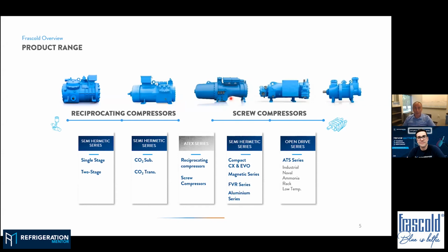Of course, the system and the charge has to be confined - it's an outdoor installation, and there are a number of safety measures to be followed. So it's not that you can put 70 pounds inside a supermarket, but it is possible. For pharmaceutical and plastic extrusion applications there's a lot of market for this compact screw compressor with propane, especially because you keep the system very simple in the end - you have a built-in oil separator, so you build it like a standard chiller with two secondary fluids, trying to keep the charge confined in a machine room that's usually external, like a containerized machine room.